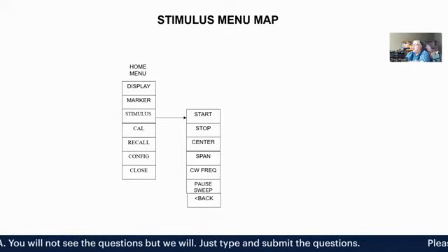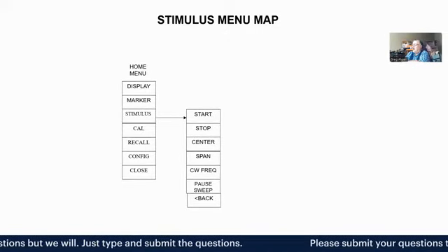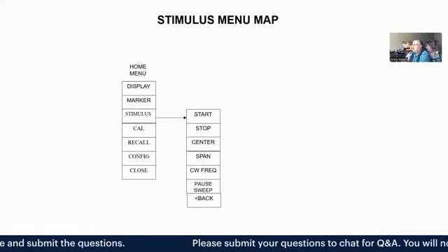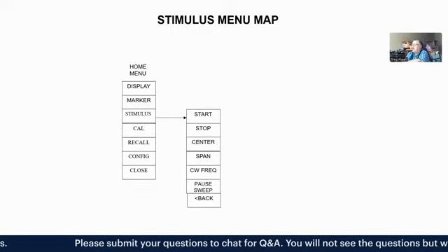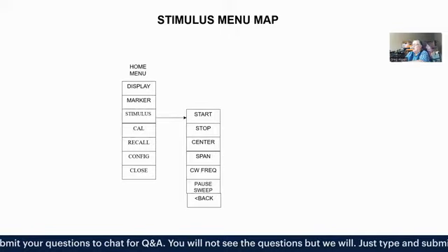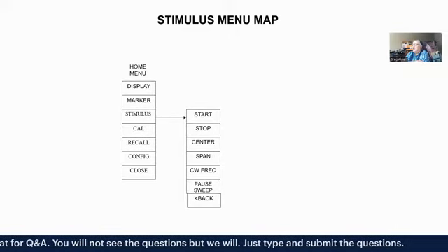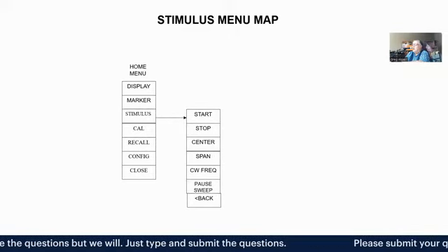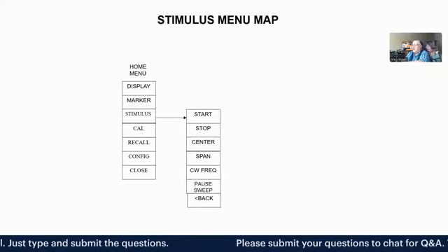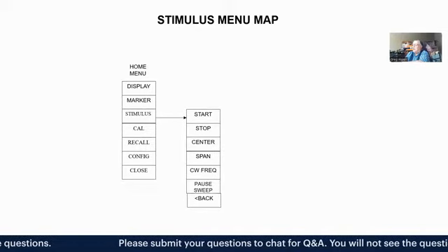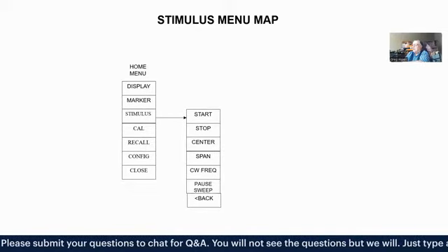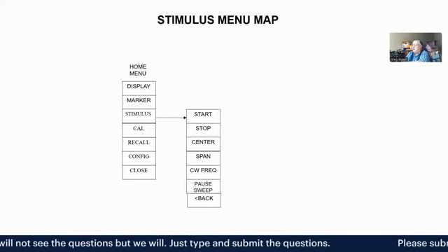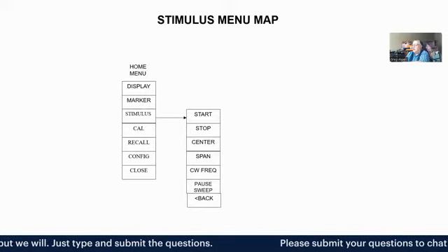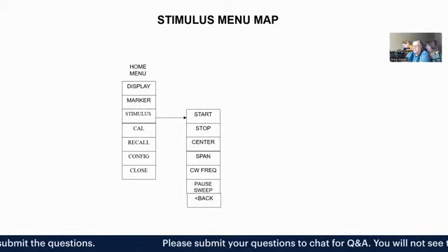Stimulus: when you're setting up the network analyzer, the network analyzer typically sweeps over a frequency range. And so you have to put in a start and stop frequency. You can put it in by entering the center and then the span, which is the width. I find putting in the start and stop is easier. Or you don't have to have it sweep. You can do the measurement at a single frequency, and that's what the CW frequency is for.